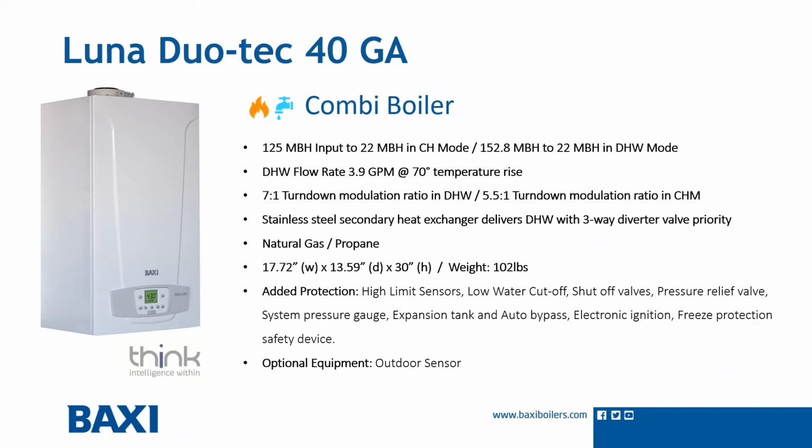Our GA40 combi unit is our most popular boiler. It has a BTU rating of 125,000 to 22,000 in central heating mode and 152,000 to 22,000 in domestic hot water mode. That means this unit will produce 3.9 gallons per minute at a 70-degree rise in temperature. The unit is 17 inches wide by 13 inches deep by 30 inches tall and weighs 102 pounds.